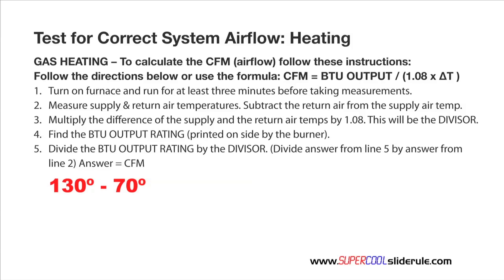We subtract the return from the supply, which will give us 60 degrees. We then multiply this by 1.08, which gives us 64.8. Now, this is our divisor. We will use this number later.